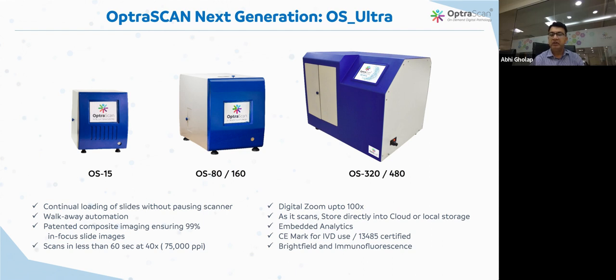And then you have an option for the continual loading of the slides without pausing the scanner. Some of the laboratories may have more than 15 slides, and that's where we have another model for 80 or 160 slides. And for those laboratories where a larger number of slides is required to be digitized, we have 320 to 480 slides scanning ability. This is a complete walkaway automation because you do not require any manual intervention here.